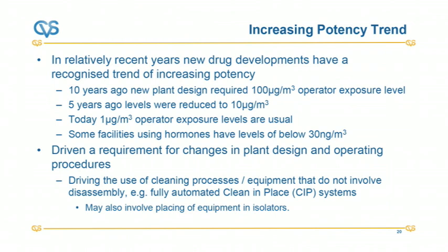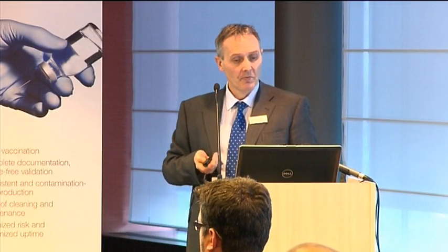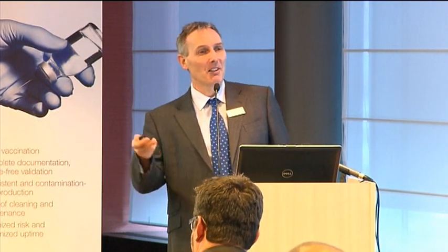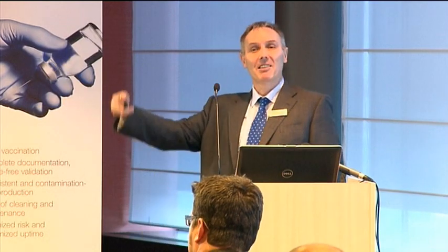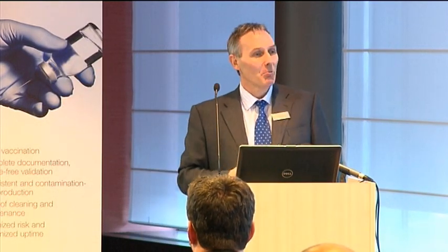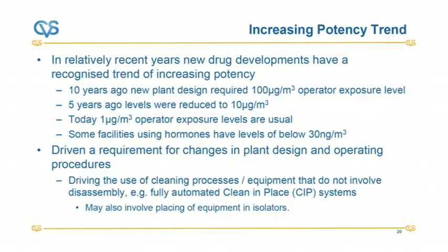And 10 years ago, in terms of operator exposure, it was probably around 100 micrograms per meter cubed. And that's slowly gone down to 10 micrograms to, in some cases, 1 microgram per meter cubed with highly active pharmaceutical materials. And if you're involved with using hormones, then you may be down to 30 nanograms per meter cubed. So this is driving a change in plant design, forcing you to move to not taking equipment apart and to having fully automated clean in place systems, which is great for spray ball manufacturers like Alfa Laval because it gives them the opportunity, but there are other people out there making spray balls. They have competition, like big pharma companies have competition from generics and things like that. But obviously they make very good quality products.